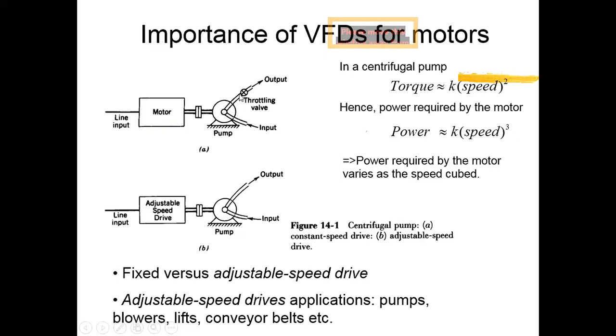Loss of energy is wasted here, right? Because it's the valve that is controlling the flow. The pump is running at a constant speed, rated speed. Whatever the flow output is, the pump energy consumption is constant. And it's a waste. The thing is, the torque is proportional to the speed squared.